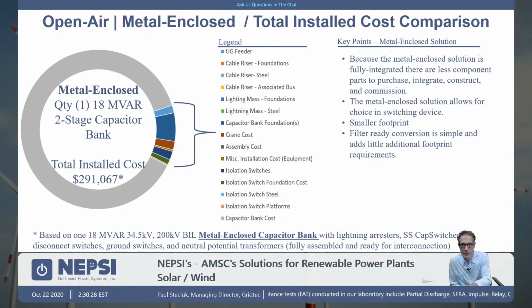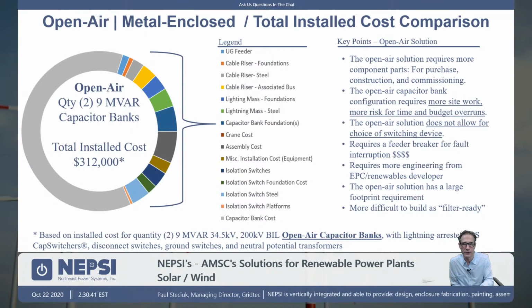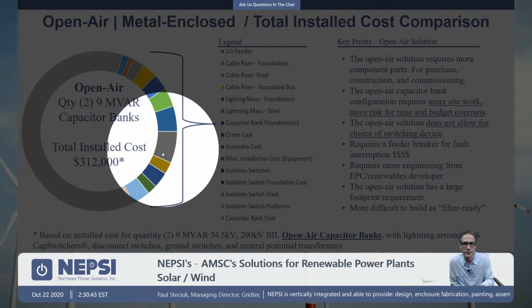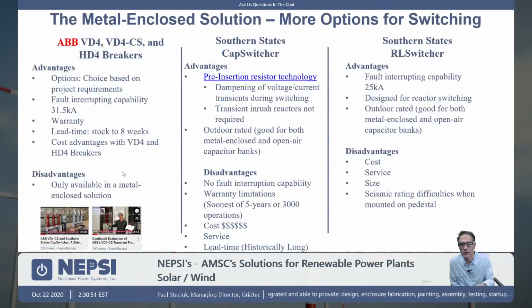It's coming to your site. You're lifting it off the truck, you're putting cables to it, and you're basically done. So the cost is incurred in the purchasing of the equipment, whereas on an open air solution, you can kind of see that the cost of the install and commissioning is a lot more, but the component cost is less. And what we have found is that more and more the metal enclosed option is becoming a preferred option because it's being understood that when you factor all costs in, the metal enclosed solution is less expensive.